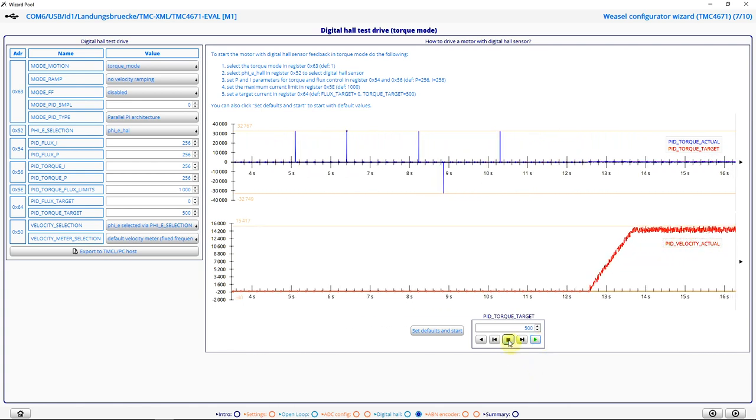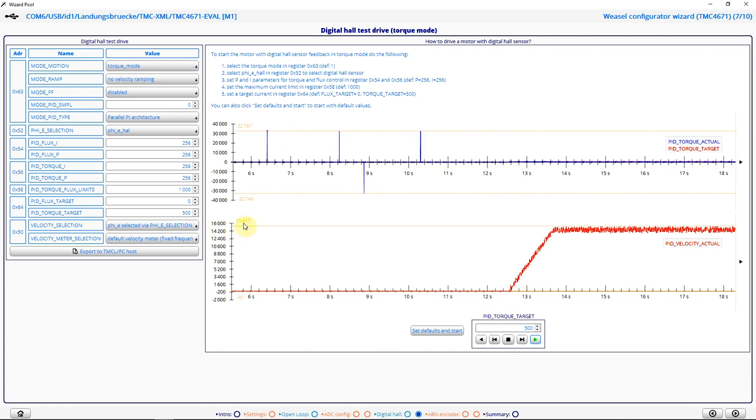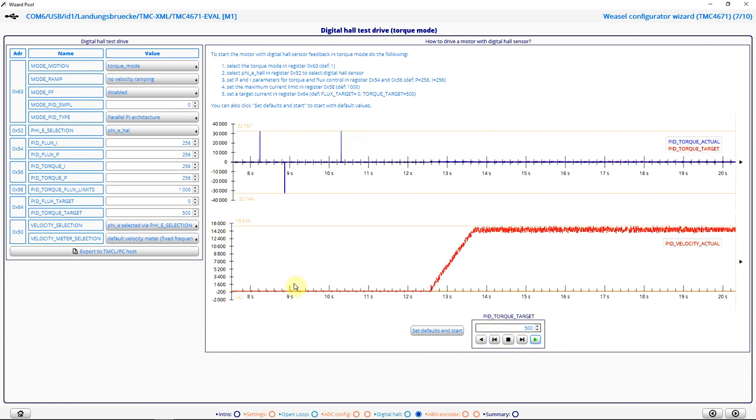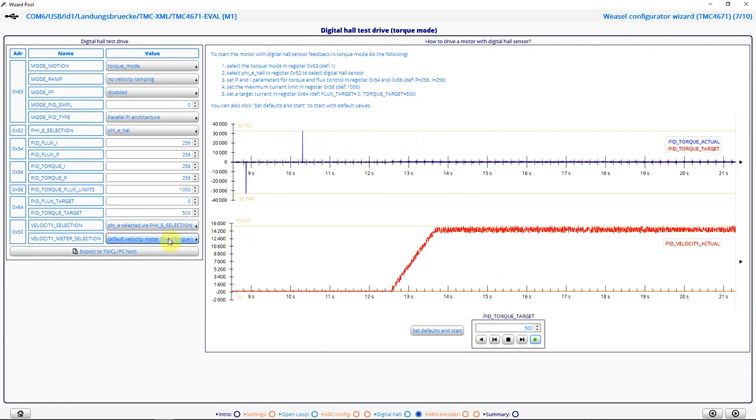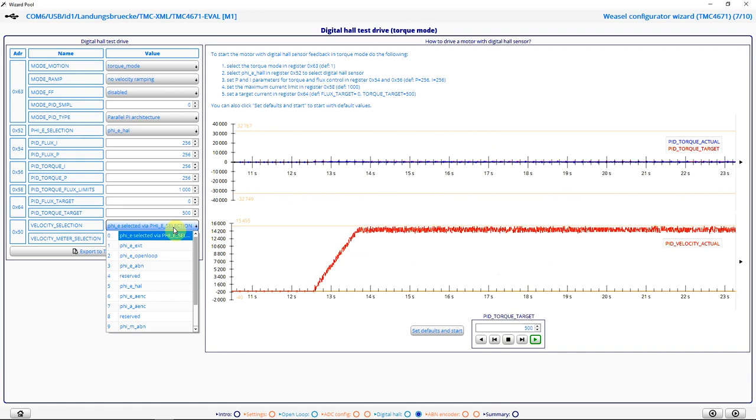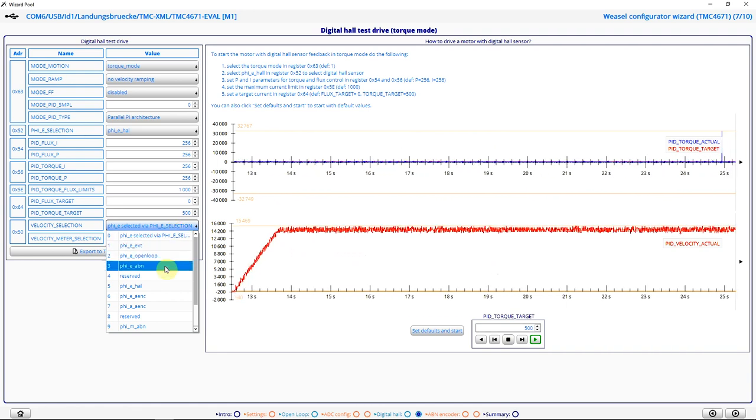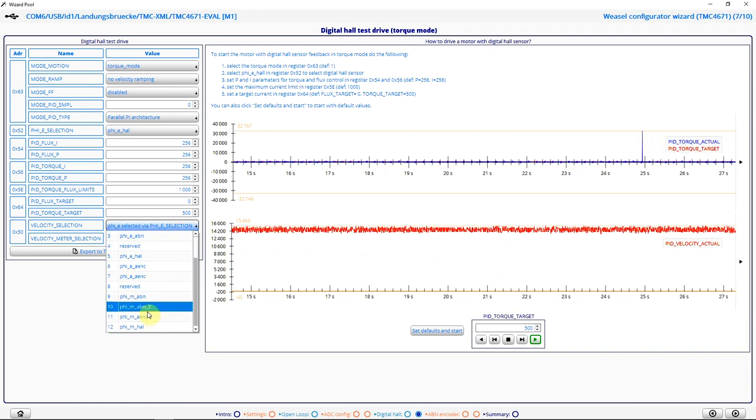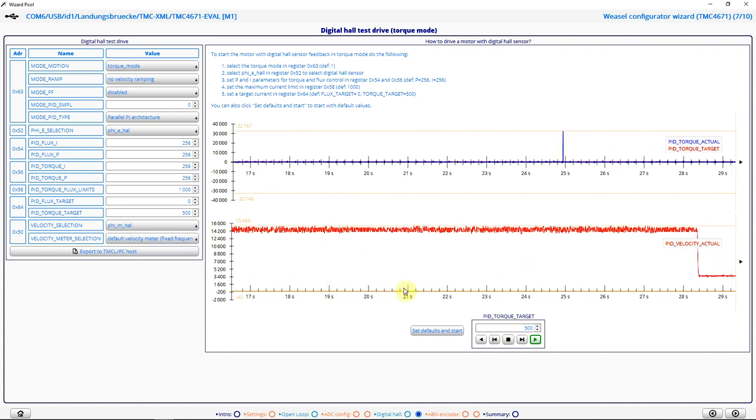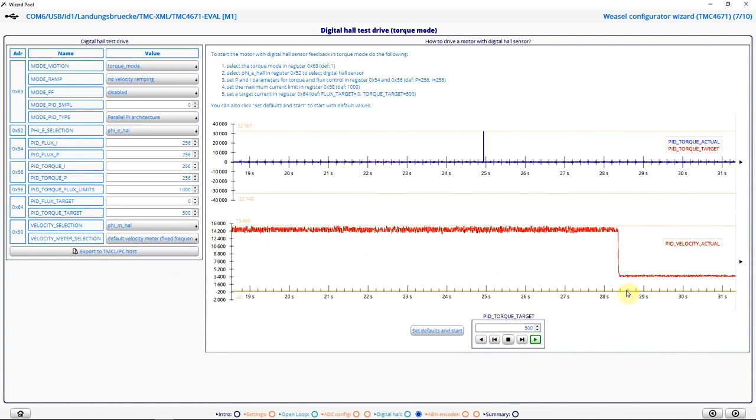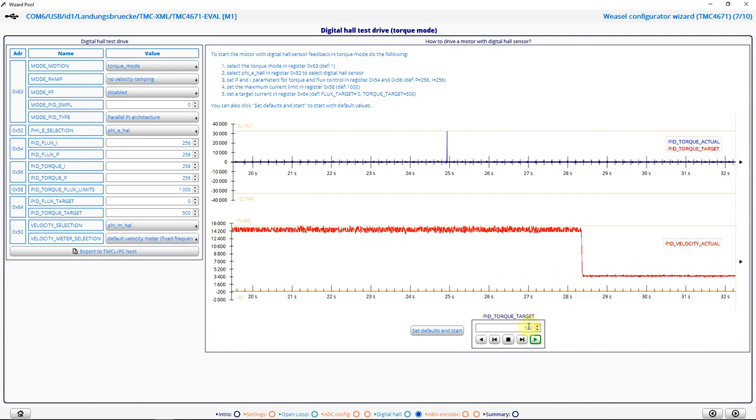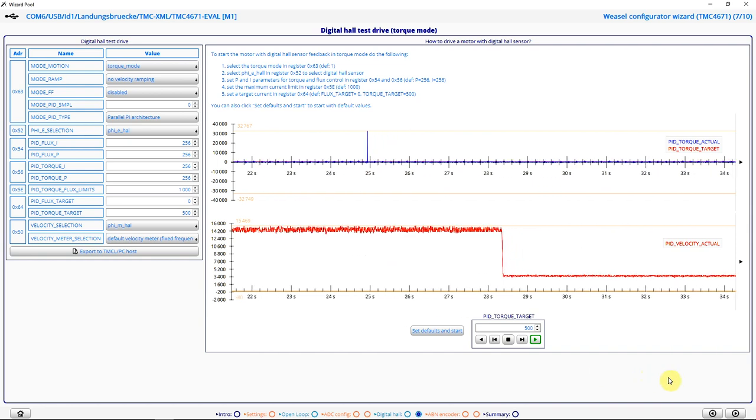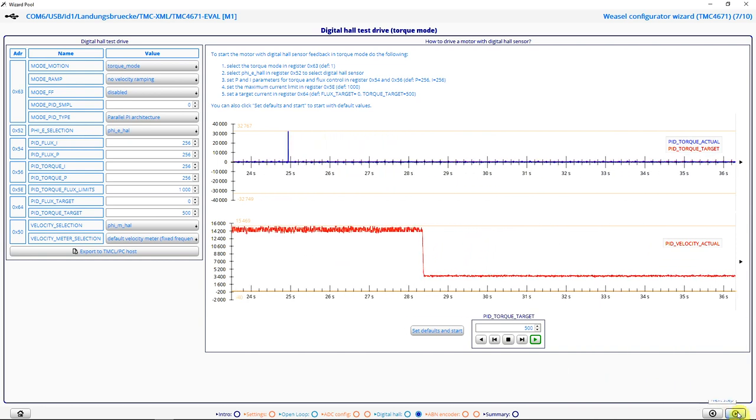And I see my velocity is quite high because I selected the phi e for velocity measurement. I can change that to phi m hall. And now I see the real mechanical velocity. I proceed with the next step.